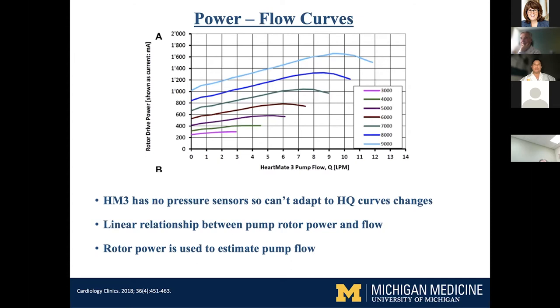The linear relationship between rotor power and flow, combined with the HeartMate 3's very accurate grasp on rotor power, means it has a very good grasp of flow — especially in the lower ranges. In the very high ranges of flow, like five or six liters per minute, it becomes less accurate, but that doesn't really matter clinically — whether the patient gets five or six liters, it doesn't matter as much.